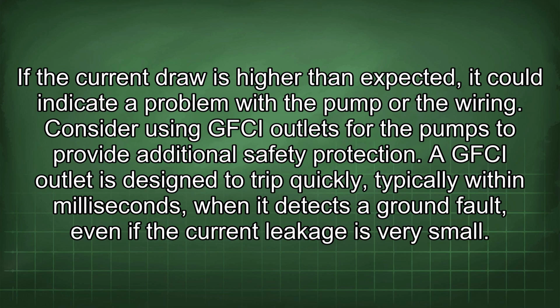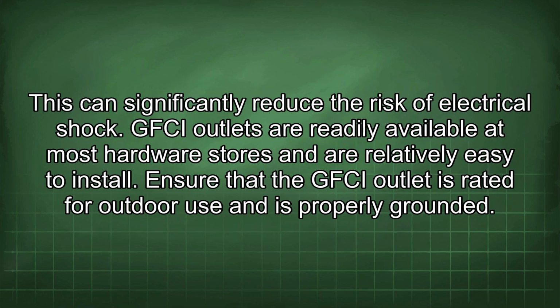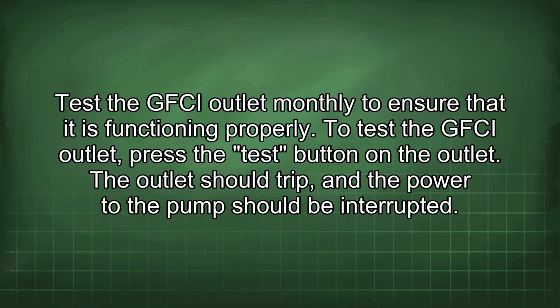Consider using GFCI outlets for the pumps to provide additional safety protection. A GFCI outlet is designed to trip quickly, typically within milliseconds, when it detects a ground fault, even if the current leakage is very small. This can significantly reduce the risk of electrical shock. GFCI outlets are readily available at most hardware stores and are relatively easy to install. Ensure that the GFCI outlet is rated for outdoor use and is properly grounded. Test the GFCI outlet monthly to ensure that it is functioning properly.